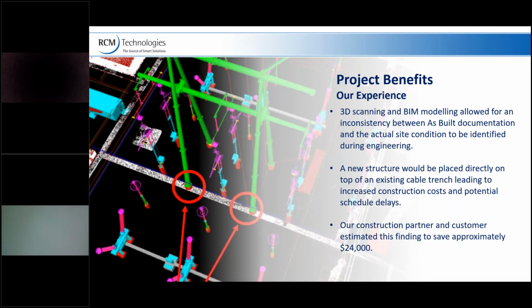Here's an example. On the right side, you can see a structure being placed directly onto a trench. The reason this wasn't found is because the as-built documentation for the substation did not match the actual condition of the site. A 3D scan of the entire site was able to identify that this clash would occur and that there could potentially be schedule delays on site. Either the structure would have to be relocated, or some design changes would have to be made, going back and forth between engineering and construction. Overall, the estimate here was $24,000 of savings just from this one finding.